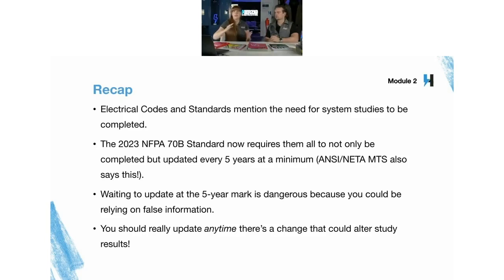So to recap this second piece, the big meat of this presentation: the electrical codes and standards mention the need for system studies to be completed, but they also require them to be completed a minimum of every 5 years, or any time something has changed, because waiting until that 5-year mark can really be dangerous. You could be relying on false and inaccurate information, or having lower PPE requirements than what's really needed because the incident energy has increased due to a change you've made.